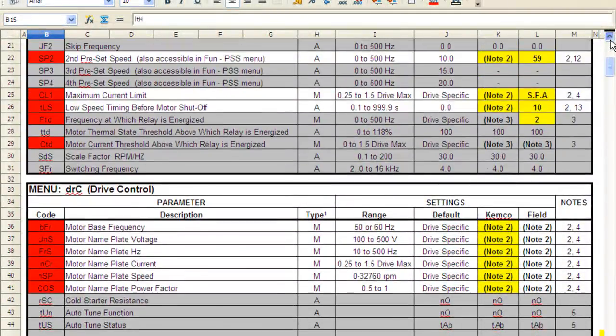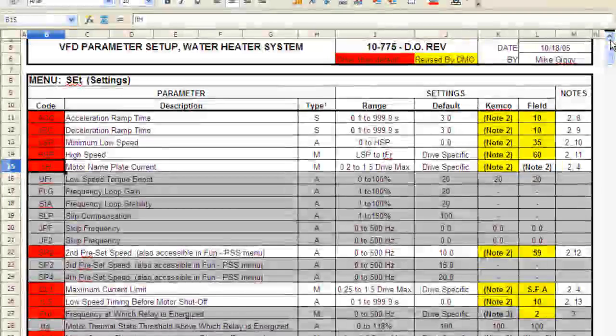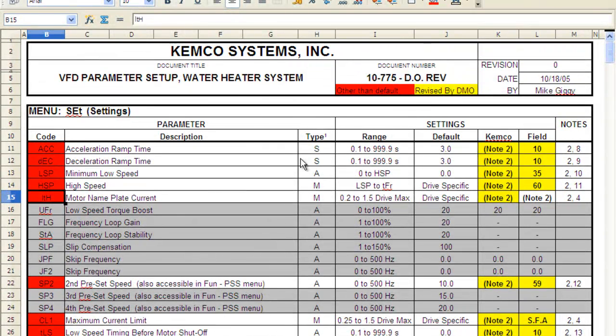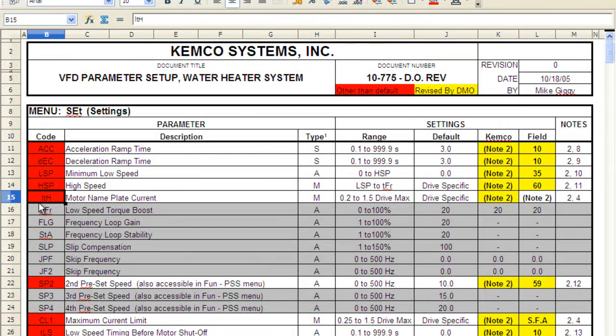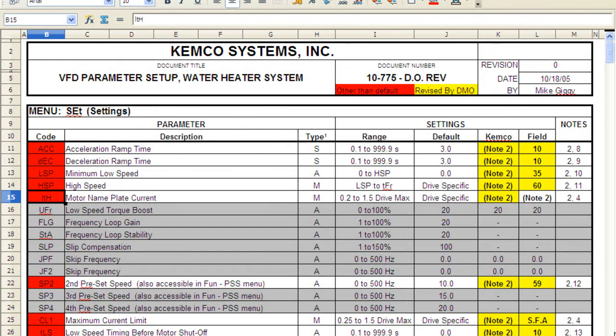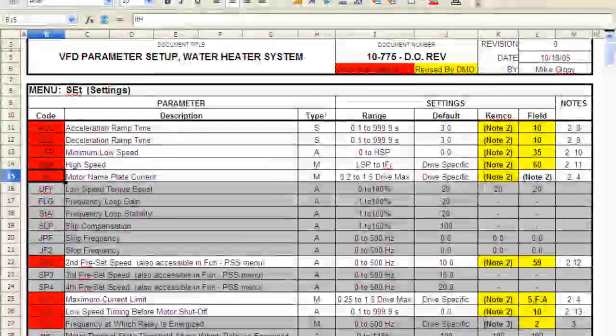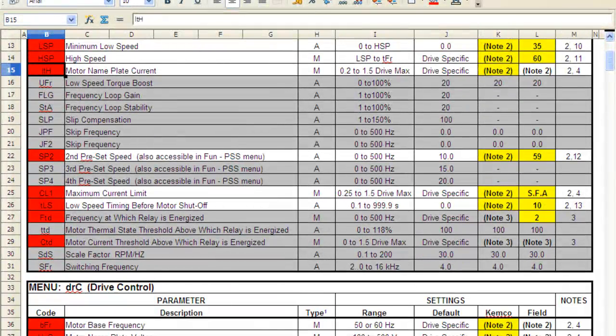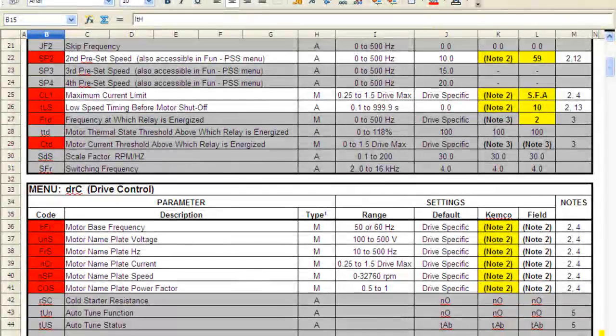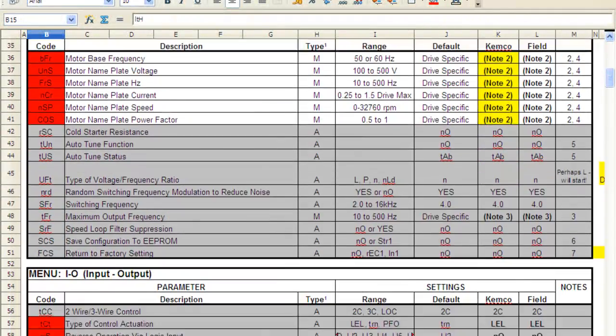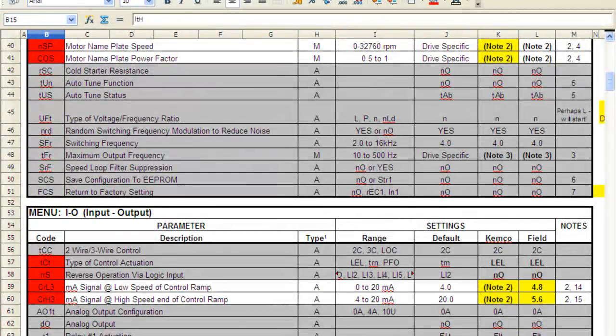Like we talked about a minute ago or so, the VFD has quite a few parameters. On this sheet, all parameters that need to be changed on a new drive are highlighted in red on this column. So if you were to have a drive fail and have to replace it, you would have to go in and change all the red parameters. The grayed out parameters you would not need to adjust.